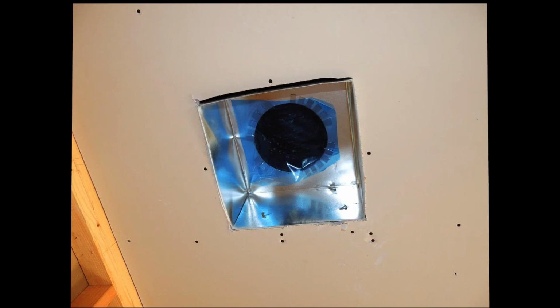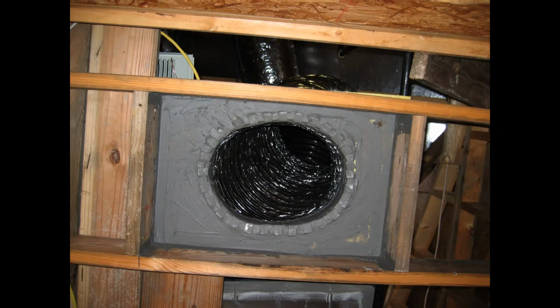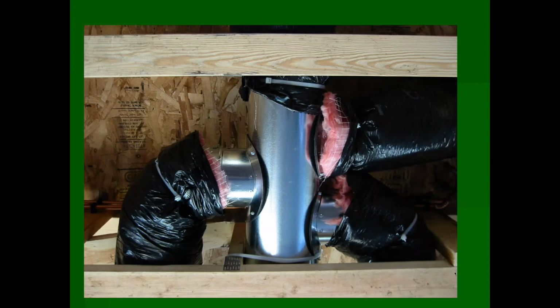Okay? So air sealing is important, continuous air sealing. Make sure that we get good proper seals. And that's all the components, whether it be flex duct or whether it be metal duct, making sure that all these joints and connections are well sealed. And these are the type of things that add up quickly in a home that really reduce its overall energy performance. So anytime you see black marks on the insulation, pretty good idea that that ductwork is not performing well.